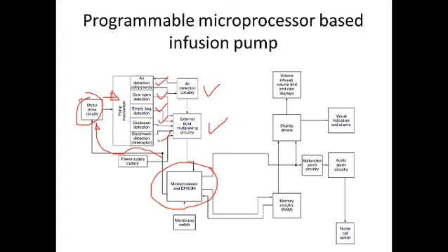For that you are also going to have a display circuit. So what will this display do? It will show the volume of the infused drug, the volume limit and rate. All these things are displayed on the display. Then some visual indicators and alarms are also connected, which will give the indication that yes, the drug was delivered.